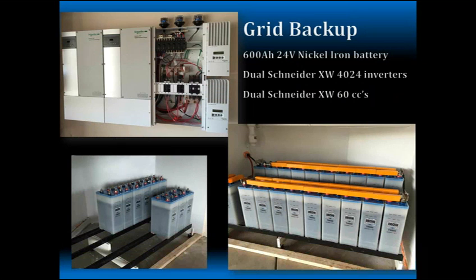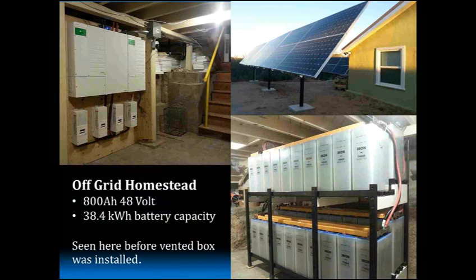Let's take a look at some pictures of battery systems using the nickel iron battery and the Schneider Electric equipment. Here you can see a 24-volt, 600 amp hour nickel iron battery. All the batteries that you'll see in this presentation are contained within a vented battery box. They photograph a lot better before we put the final touches on the box, but please know that it is important to vent the nickel iron batteries using the vent fans that we include in our complete systems. In this particular system, we have two Schneider XW 4000 watt inverters. We also have two 60 amp Schneider Electric charge controllers.